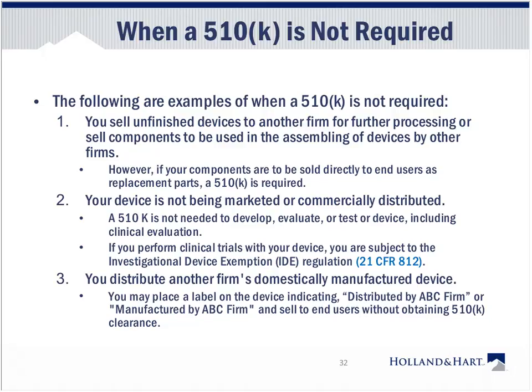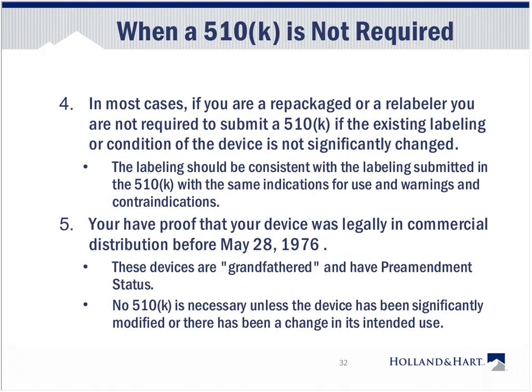That does not require a 510K pre-market notification clearance. In most cases, if you are a repackager or a relabeler, you are not required to submit a 510K if the existing labeling or condition of the device is not significantly changed, just what we said a moment ago. You have proof that your device was legally in commercial distribution before May 28th. Those are grandfathered in. Again, a 510K is not necessary unless the device has been significantly modified or there has been a change in its intended use.